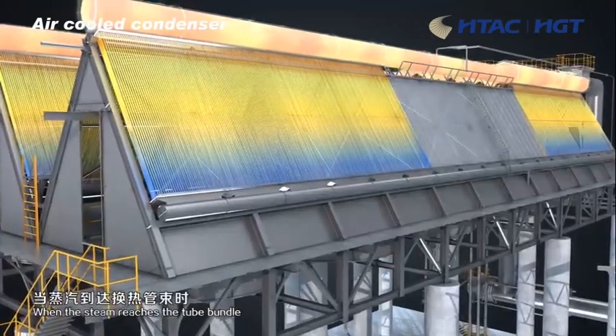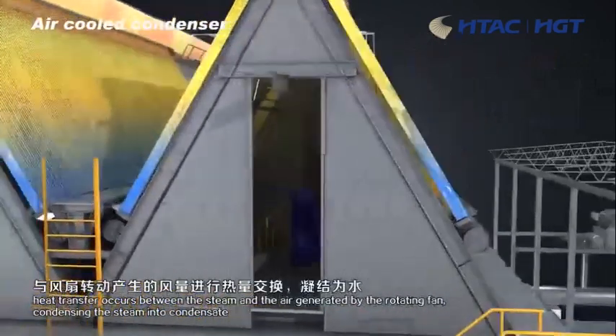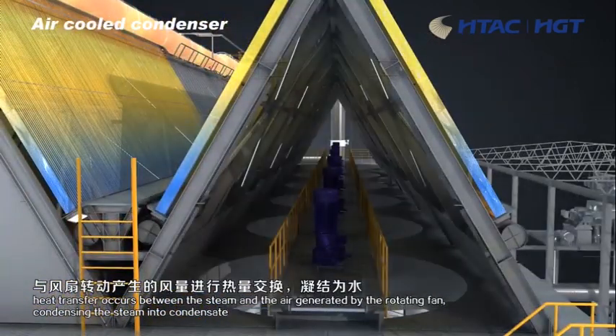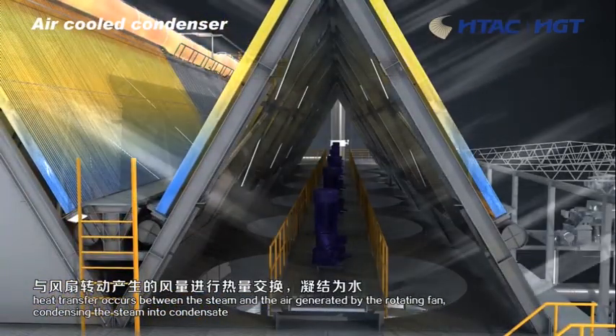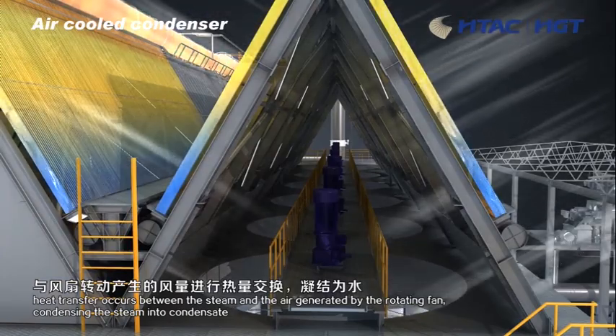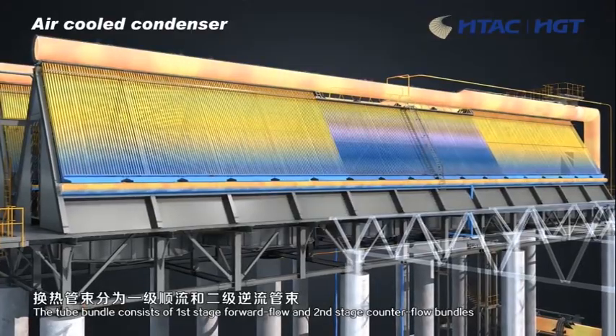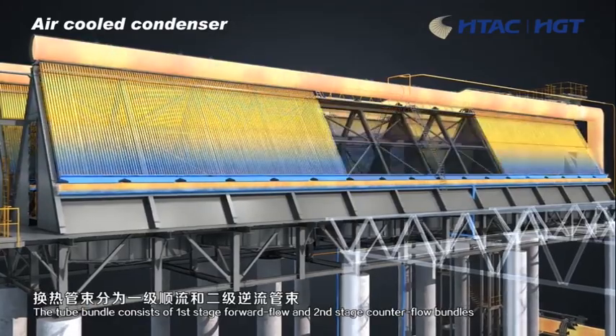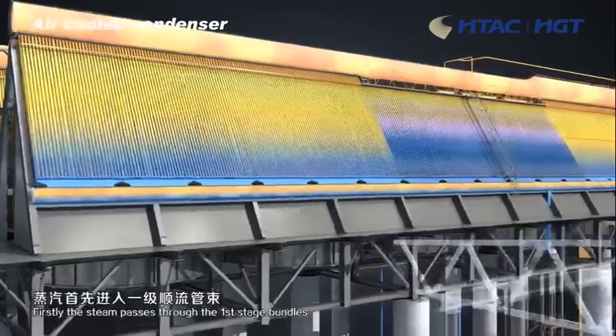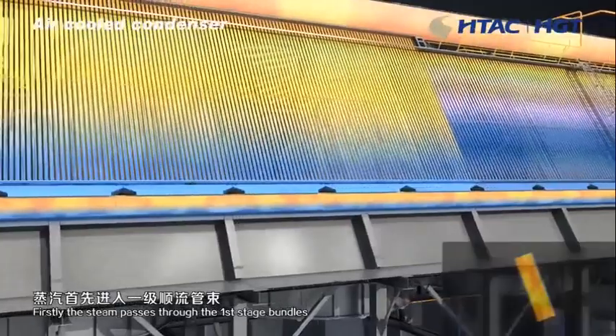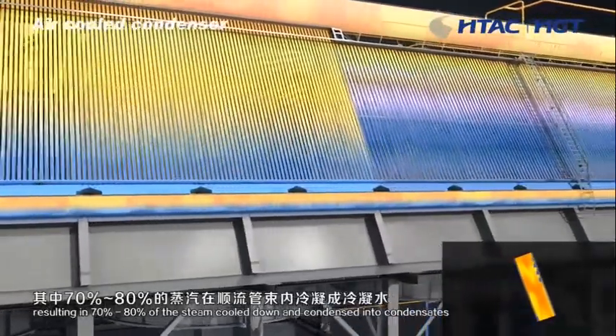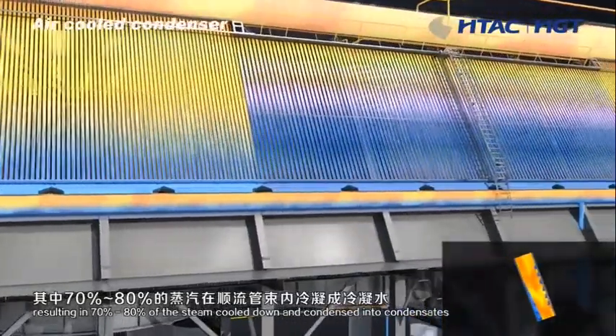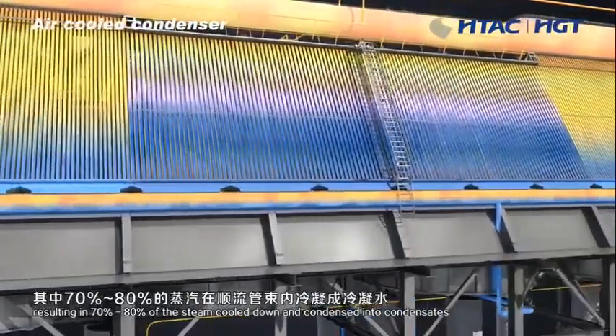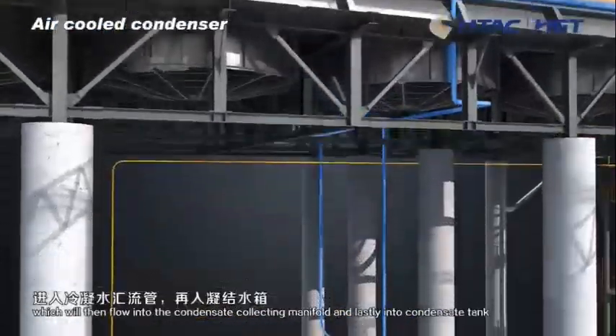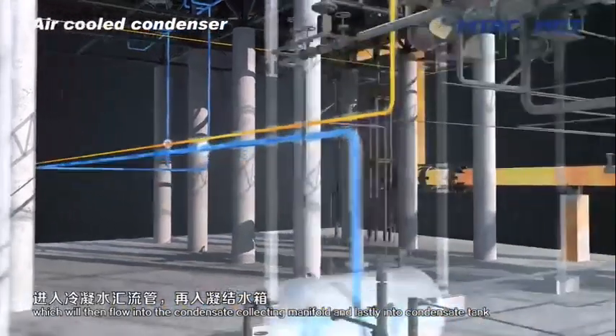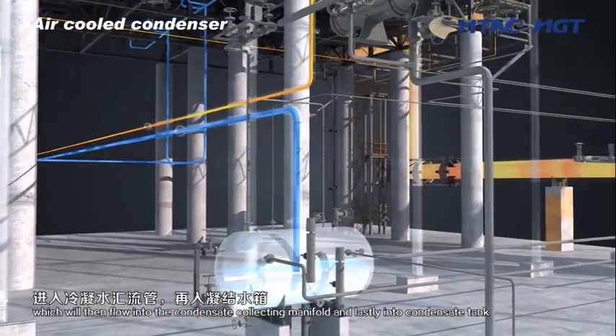When the steam reaches the tube bundle, heat transfer occurs between the steam and the air generated by the rotating fan, condensing the steam into condensate. The tube bundle consists of first stage forward flow and second stage counter-flow bundles. Firstly, the steam passes through the first stage bundles, resulting in 70% to 80% of the steam cooled down and condensed into condensates, which will then flow into the condensate collecting manifold and lastly into the condensate tank.